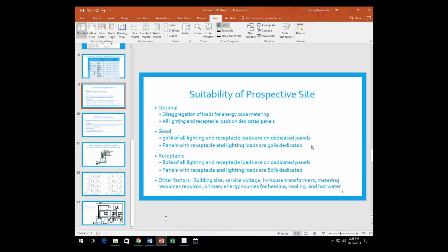There's one thing I'd like to consider, but I don't really think it's within the scope of this project. I like the actual idea of metering at the panel boards—it can give you a handle on how much your load is actually on there. There's an article in the NEC that says if you have the demand, you multiply it by 125% and then round those numbers up. Say you had a 150 amp main breaker on the panel and 100 amp demand, you'd still be allowed to add 25 amps to it. It gives you a better handle on what's going on.